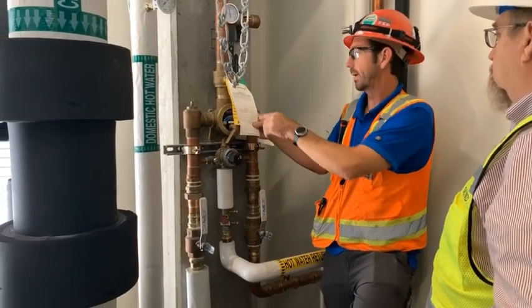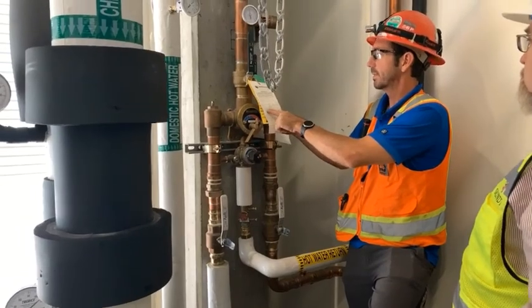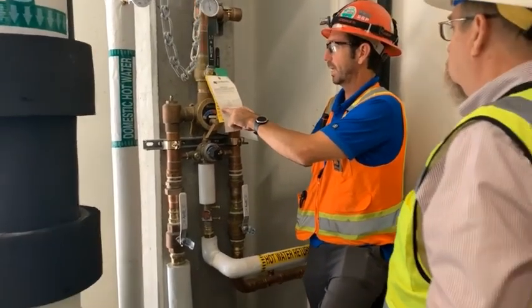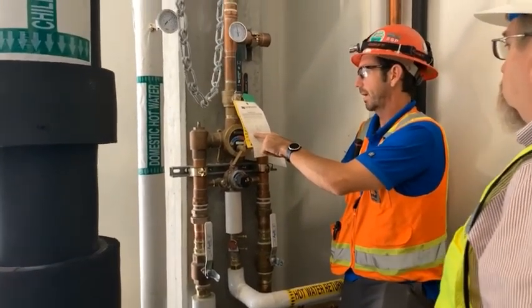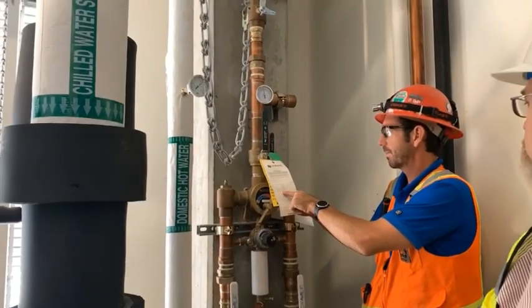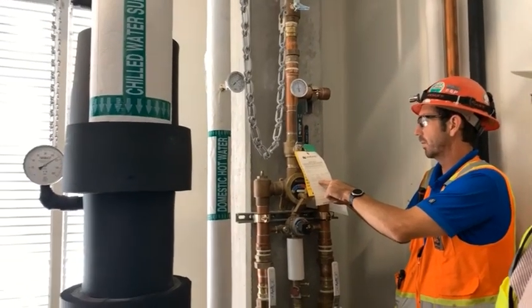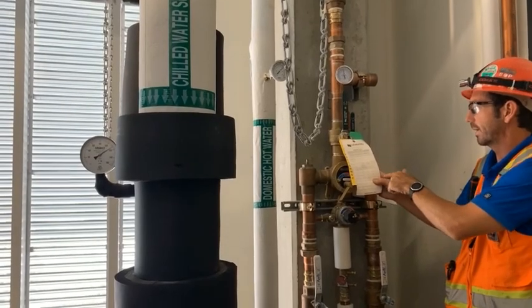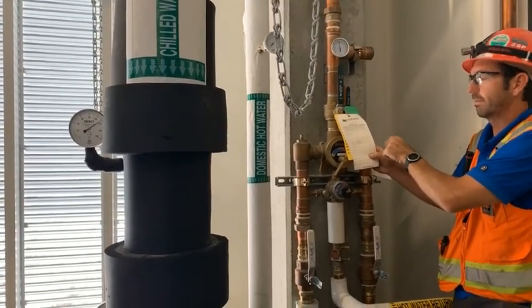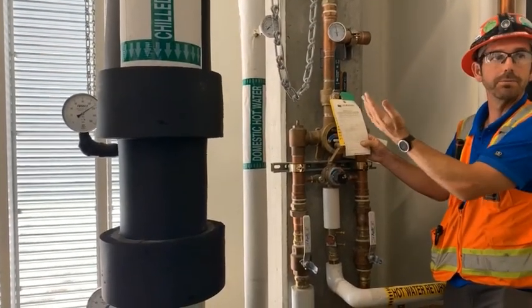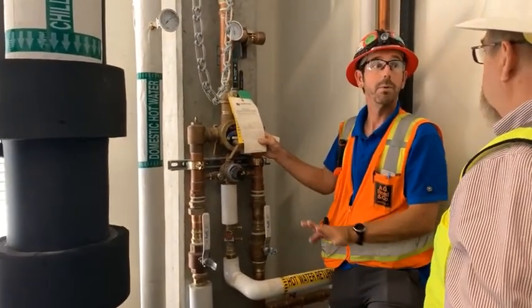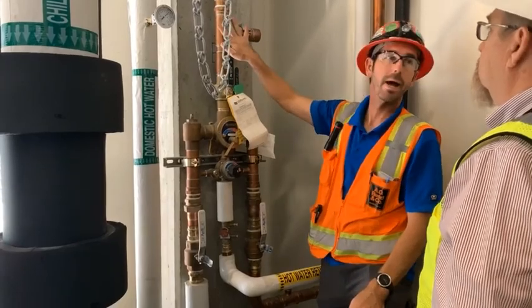Just make sure you look at all this. Just the date inspected, you can put the name or not. If you've done any work on the valve, I would also add another column for the temperature, just so you can record temperatures. So every day you want to switch it on and switch it off? No, just inspection, just to verify that the temperatures are right.